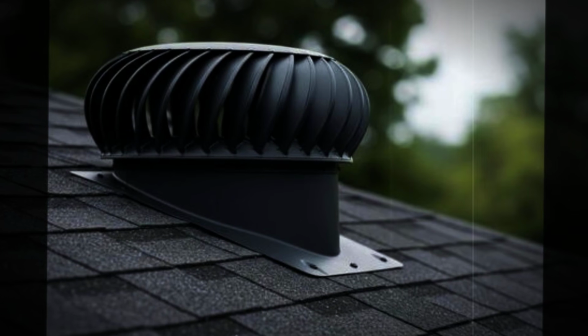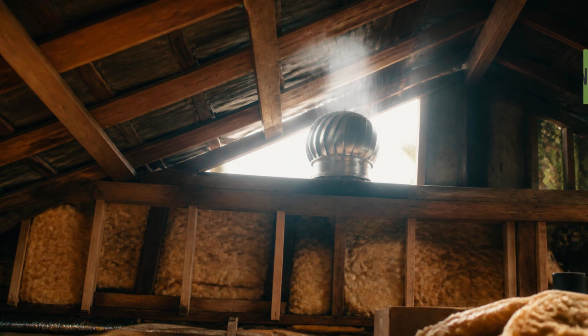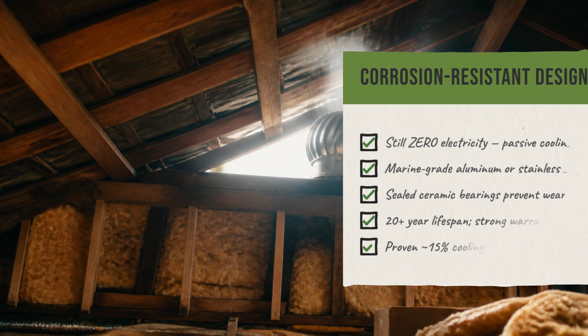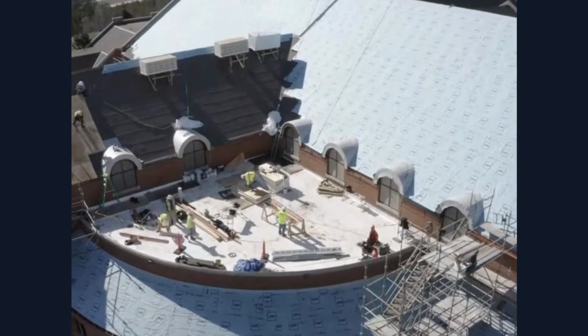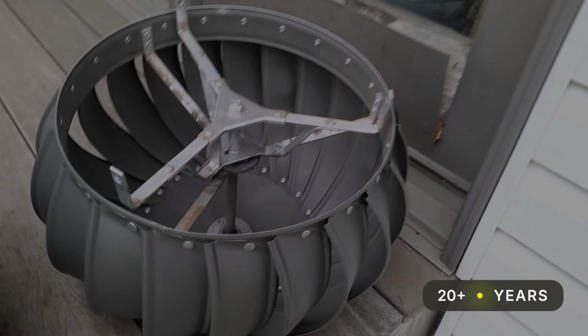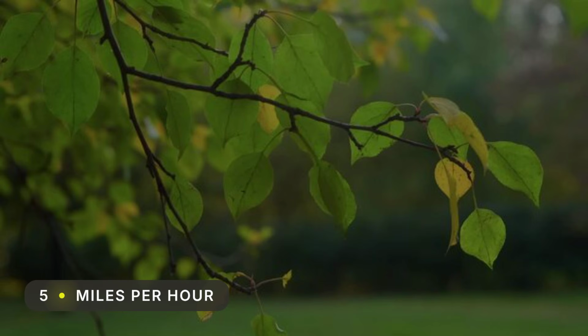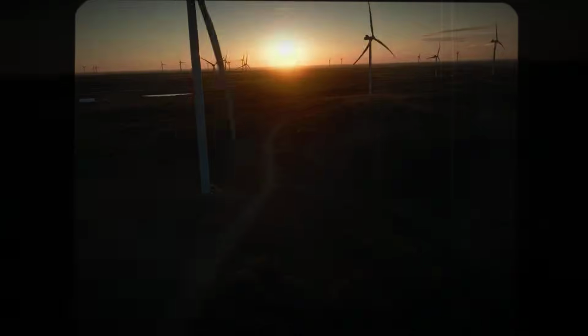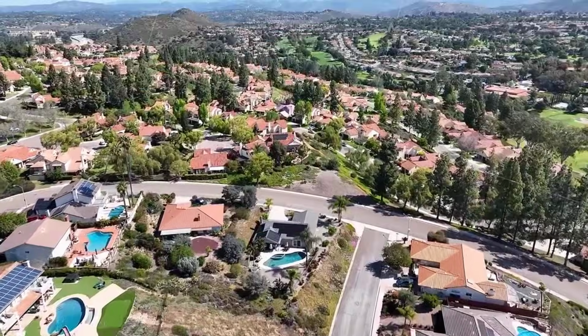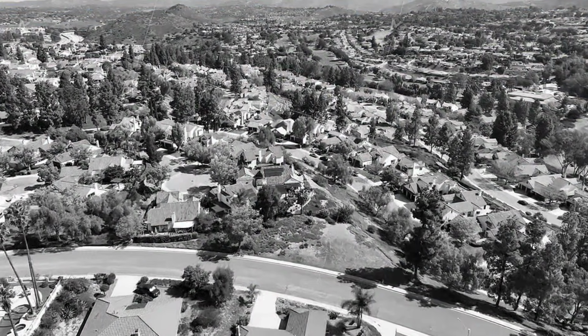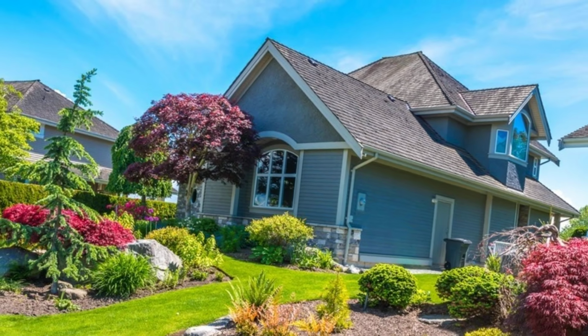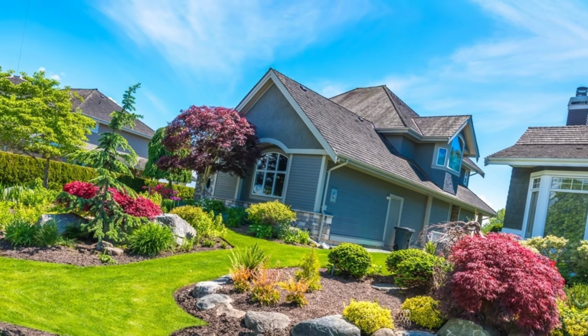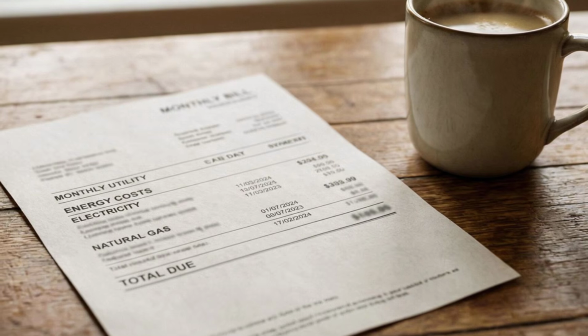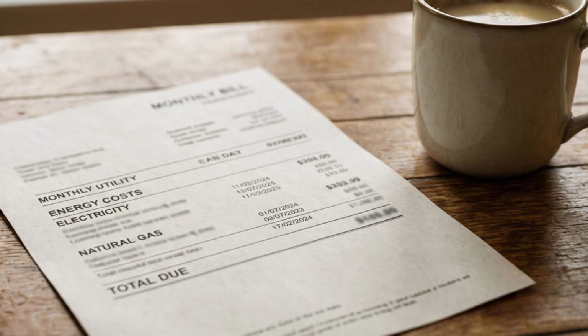The core value proposition of the turbine ventilator has not changed. It remains a zero electricity device that uses wind energy and thermal buoyancy to continuously exhaust hot air from the highest point of the building. A standard 14-inch unit moves between 350 and 500 cubic feet of air per minute at just 5 miles per hour of wind. It costs nothing to operate. It produces no carbon emissions. And in a hot climate, it works every single day from the moment temperatures begin climbing in spring until they drop in autumn without any intervention required. The energy math remains exactly as compelling as it was in the original data.